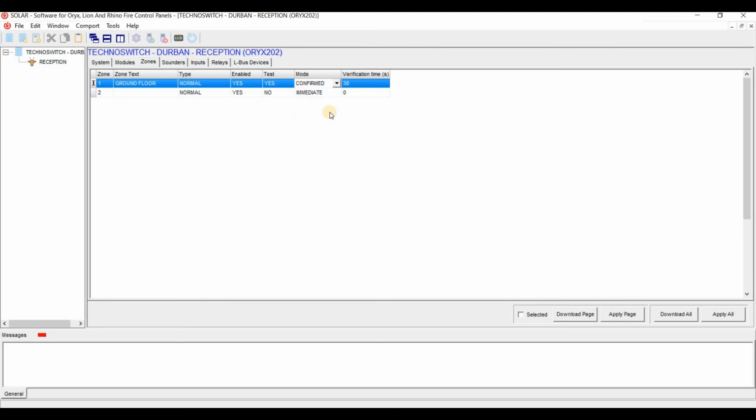The same thing has happened, an optical smoke has reached its threshold, and effectively what happens is it will then continue to check for 30 seconds for that threshold and continue to do so for the next 30 minutes on a cycle of every 30 seconds. And if it's still not being met, that will simply be cleared off the panel. It will not be displayed.